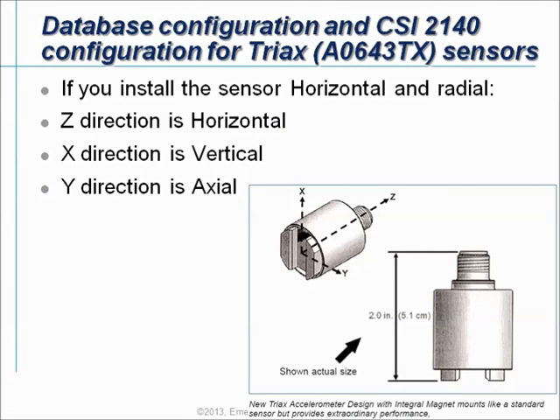If you work with a Triax sensor, you can use it in different methods and you can also install it in different directions. In this video tutorial we will focus on one practical case where we will install the Triax sensor always in horizontal direction and in radial direction on the machines. If you are using the CSI Triax sensor A0643TX, you see an image here of the Triax sensor. It has an embedded magnet. The Z direction is our horizontal reading, the X direction is a vertical reading, and the Y direction is an axial reading.